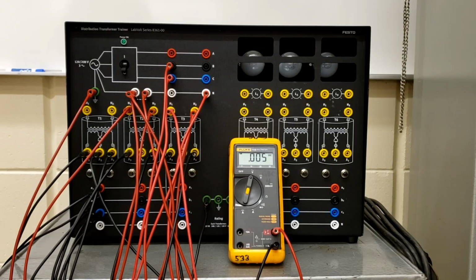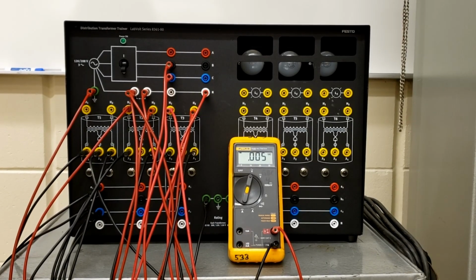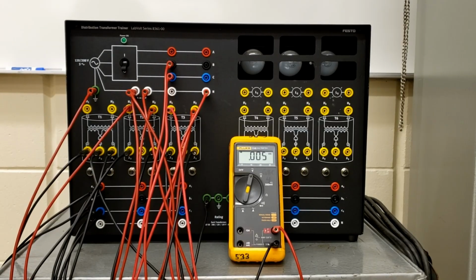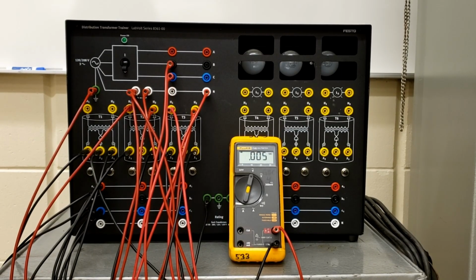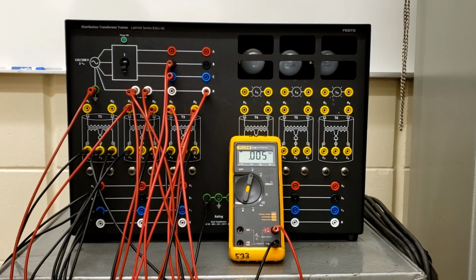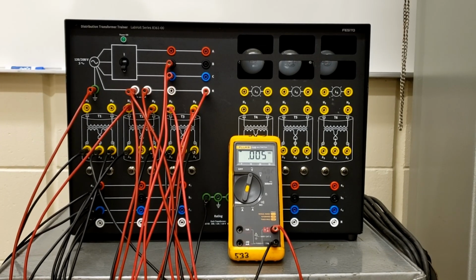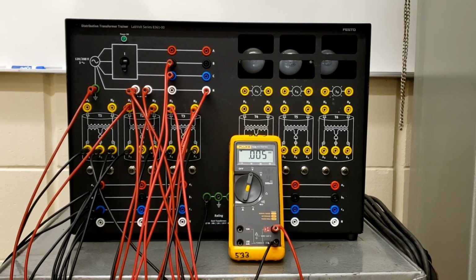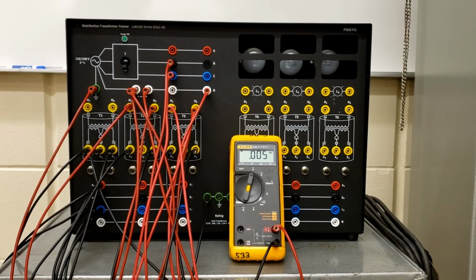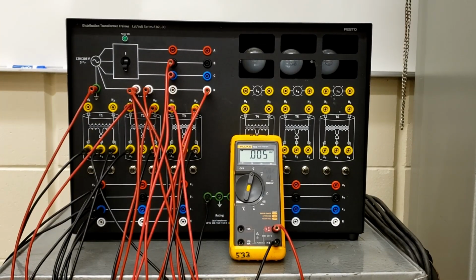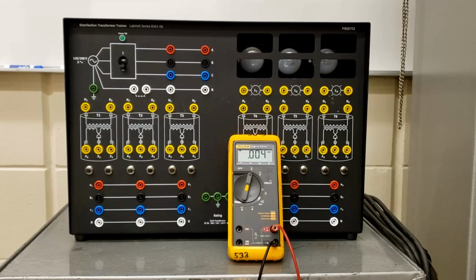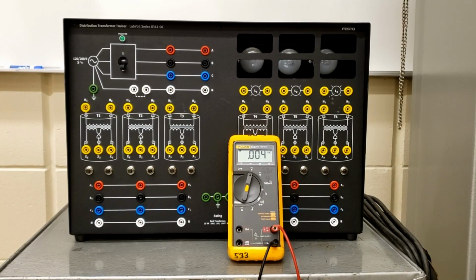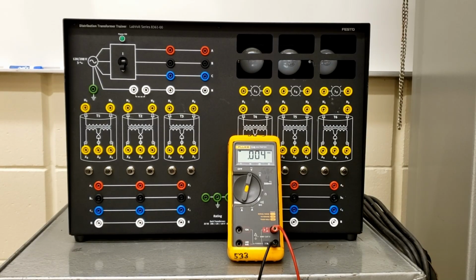Okay, moving on to the next page, on page 20, do your results demonstrate that it's possible to supply a three-phase load with only 2 transformers? Yes, if you have an open Y, you are able to do that. The issue is that again, you're going to be reducing the amount of power that's available on the secondary side because you've essentially eliminated one of the transformers there.